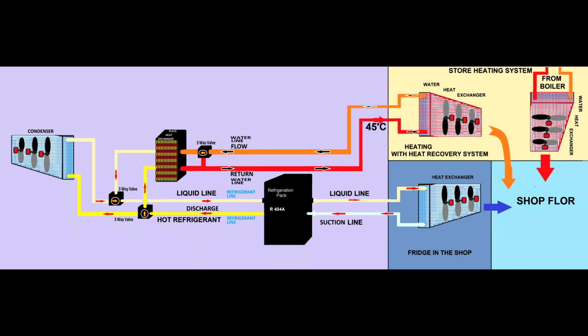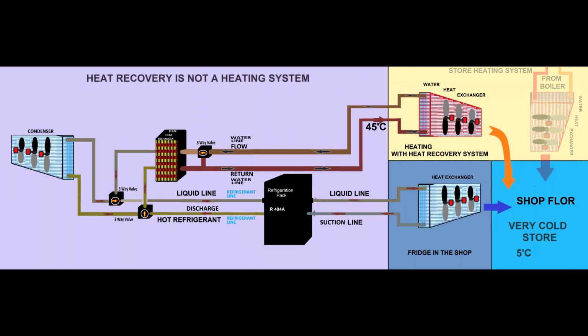So guys, it is very important to remember this. A heat recovery system is not something that creates heat. It will only recover the heat. I personally experienced problems with people who don't understand what heat recovery is for. Imagine that if you do not have a source of heat in the store, then there will be nothing to recover, and your store will become extremely cold, and of course the refrigeration equipment will not have to work hard at all because the product will be cold all the time. Then you will complain because your store is very cold.